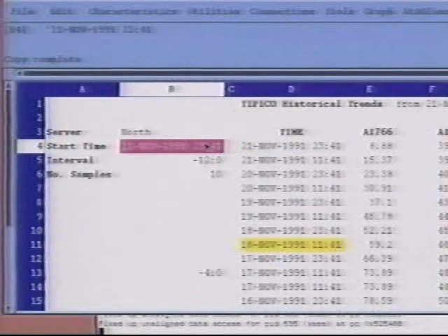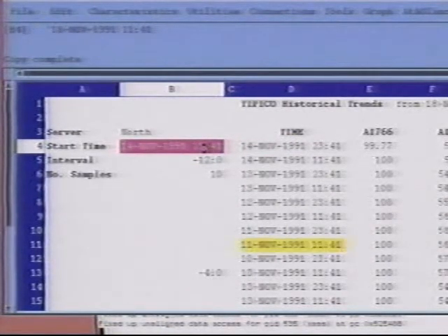Now, what we're going to be doing is looking at the history of 5 of my process variables over the last 6 days. Currently, I'm using an engineering spreadsheet called Excess. Just as with Lotus 123, At a Glance has allowed us to connect this spreadsheet directly into our control systems. Okay, Charlie, let's look a little further back.